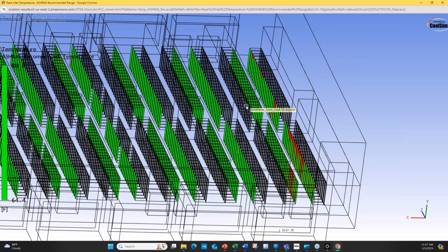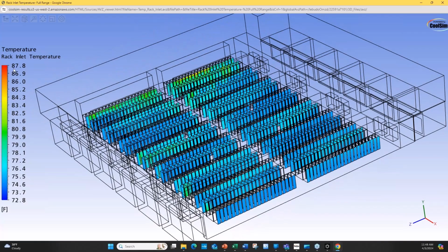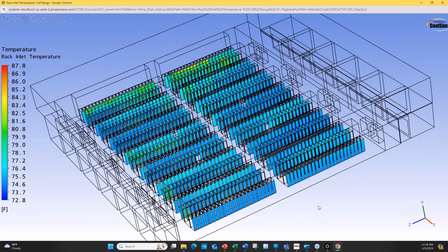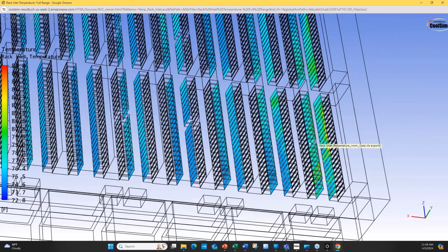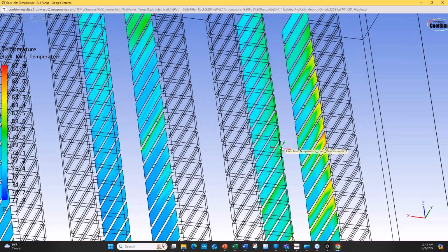But is it fair to say, Paul, that this graph might overemphasize the problem because it's green or red, but in reality, that over temperature we see that the red areas, they are just marginally warmer than the rest of the room? That's right. You are right, and that's why we also include this full range. So here's the full range, and the full range takes, like you said, max and min of the entire room. And let me flip it around so we're looking at it the same way again. But here, same section. And you see that it's a contour.